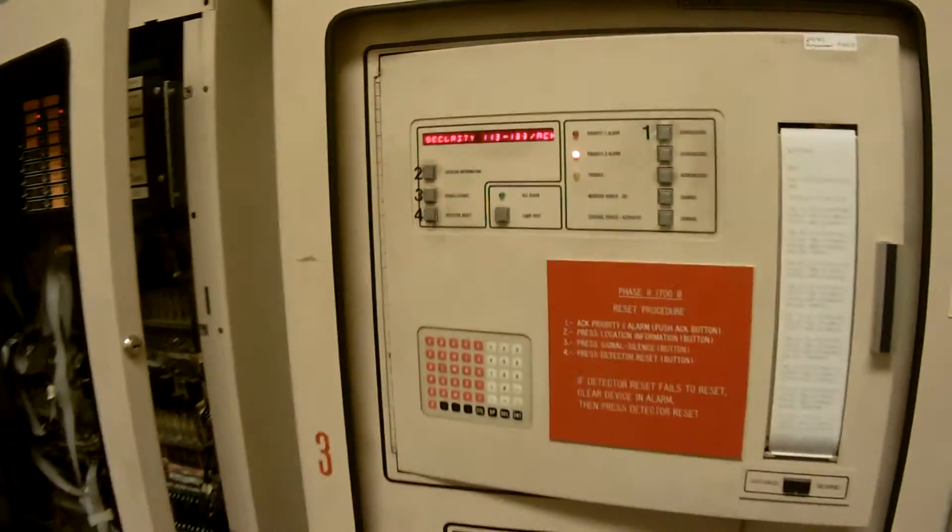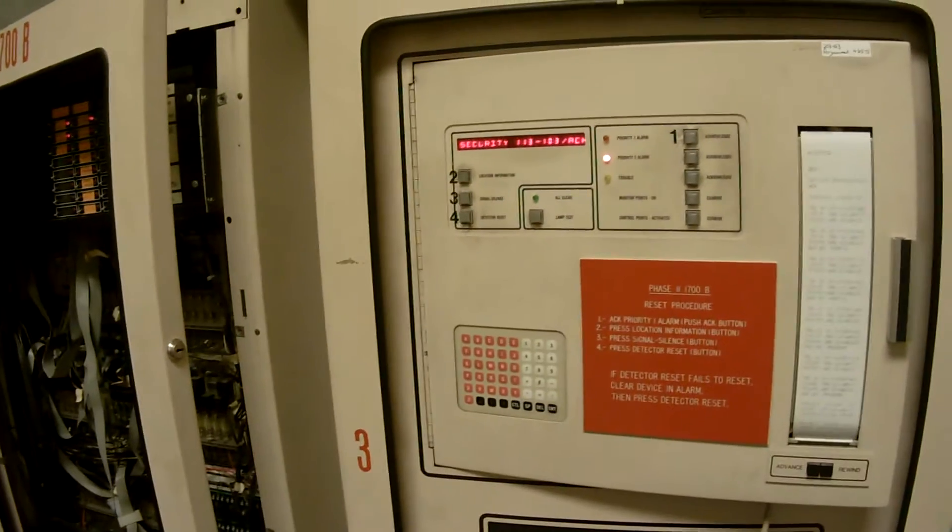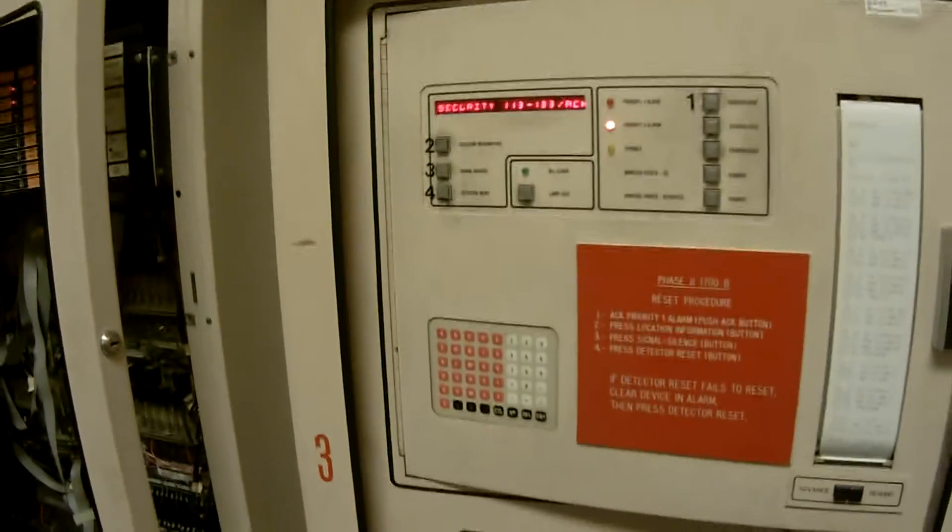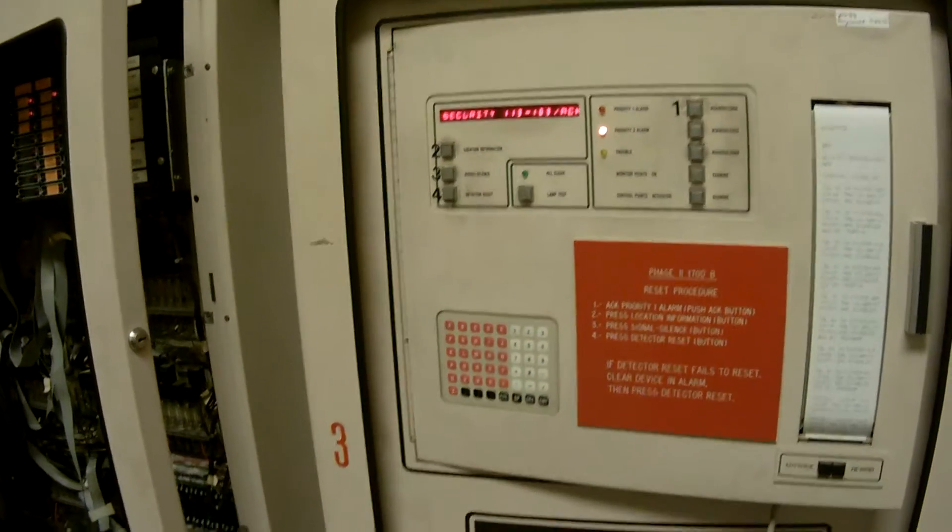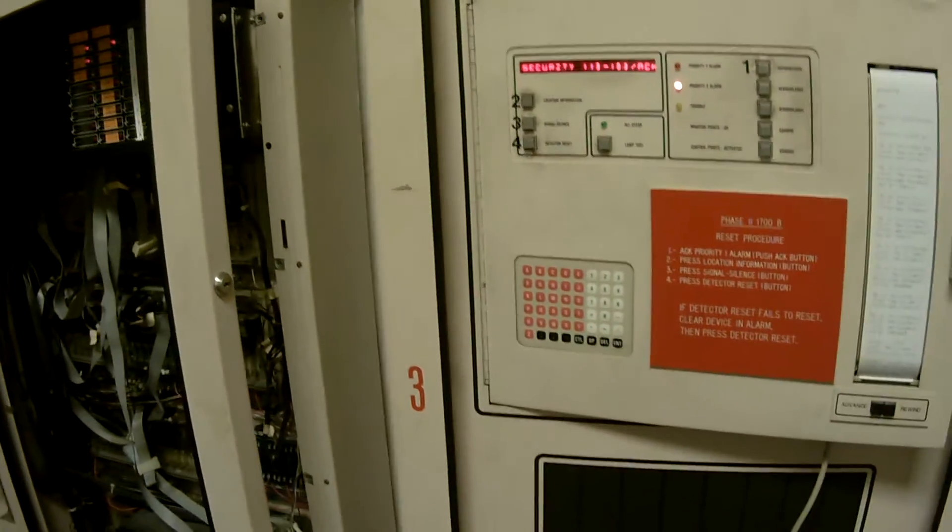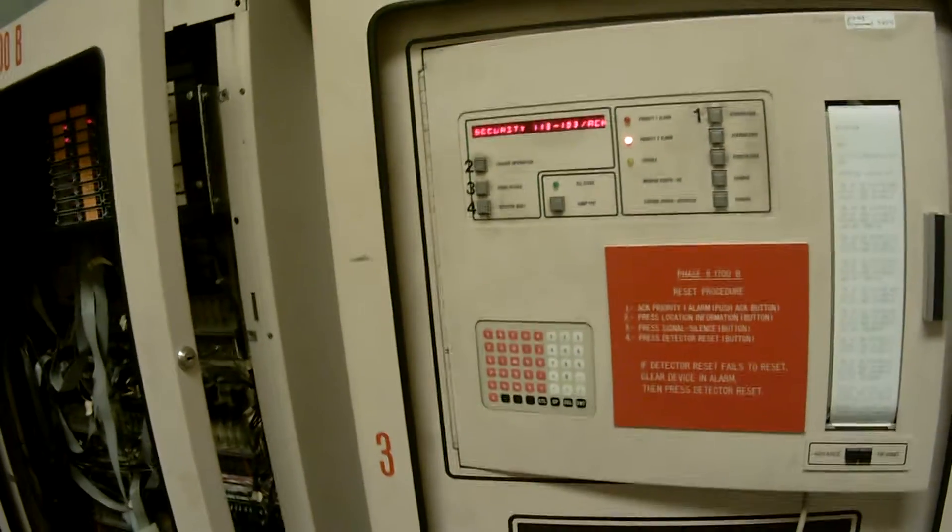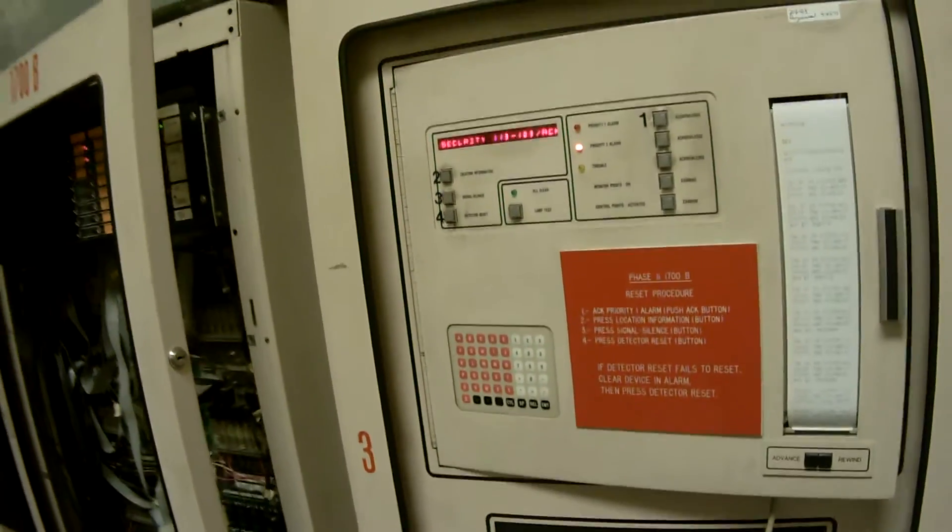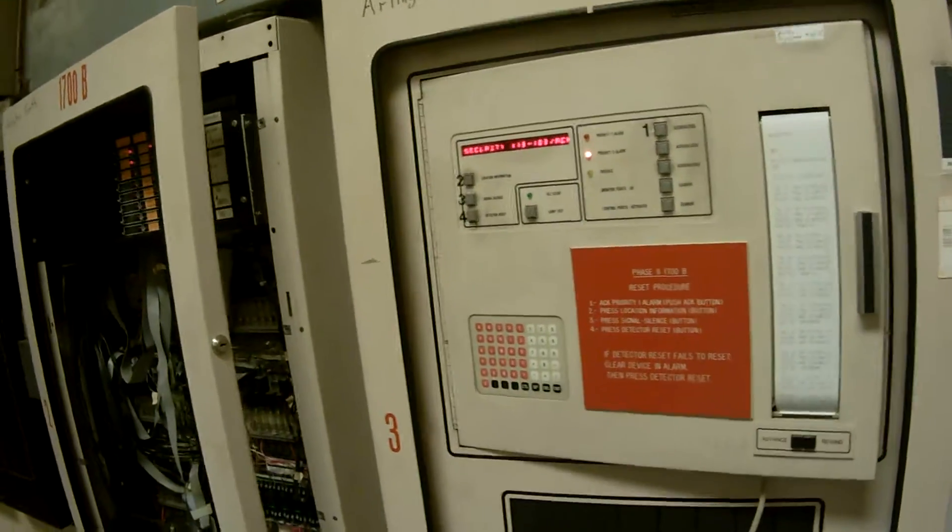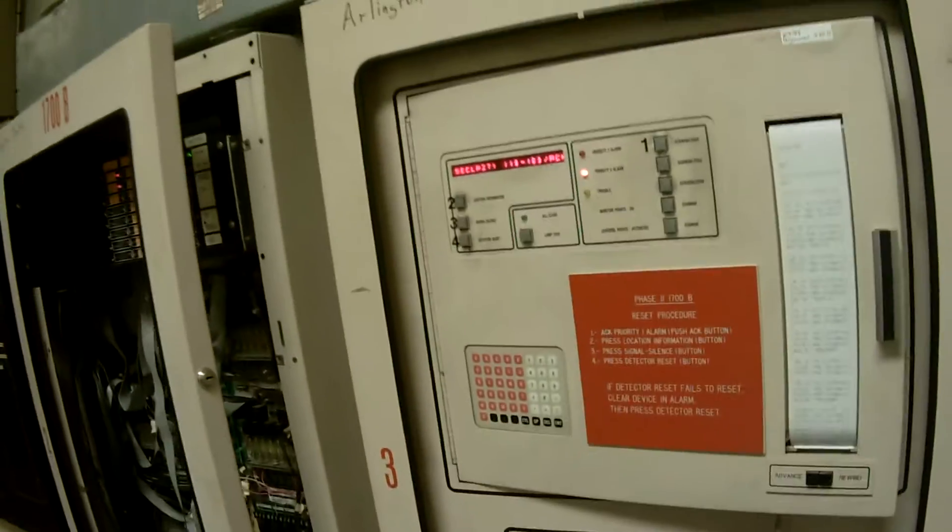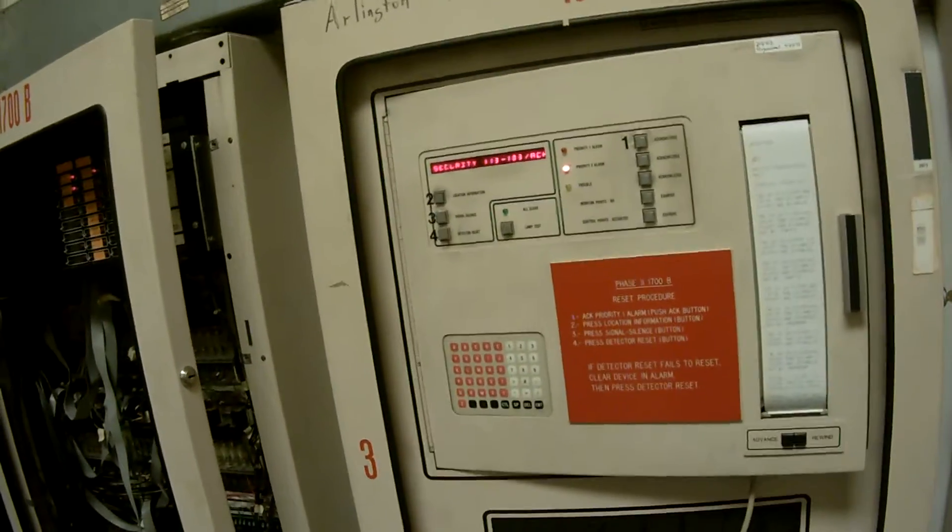One thing about this panel, you'll notice, is the green light is not on. The green light is not a power on light, as in a 4100 panel. The 4100 panel, the green light signifies that you have 120 volts power going to your panel. All clear will come on when everything else is out. That is signifying that everything is 100% in that panel.